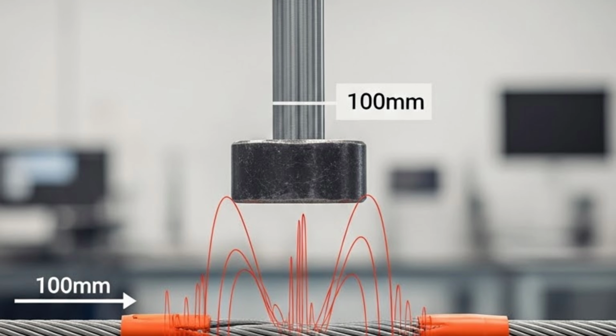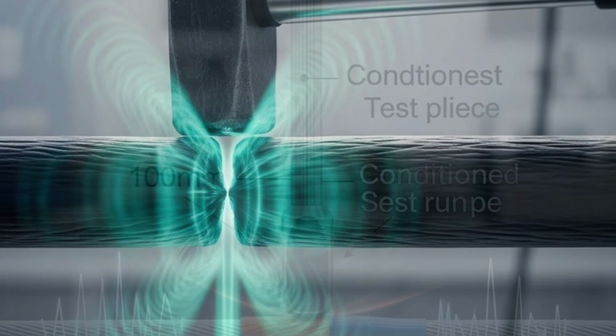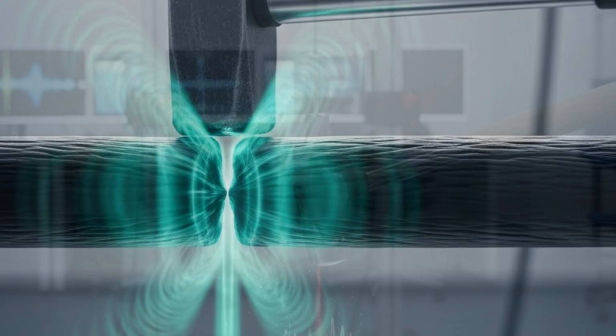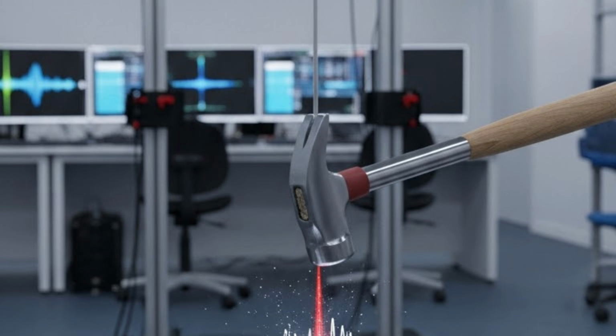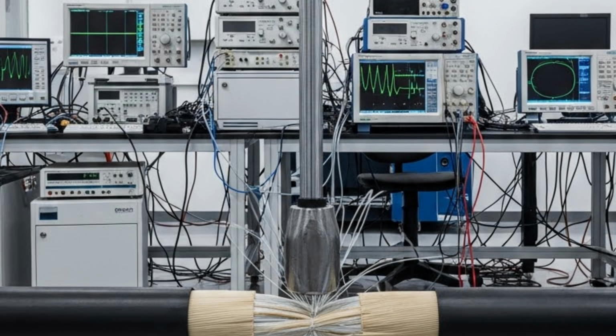Test procedure. After conditioning, each test piece is placed on the steel base. The hammer is released from 100 millimeters height, impacting the cable. This process is repeated for all 3 samples.